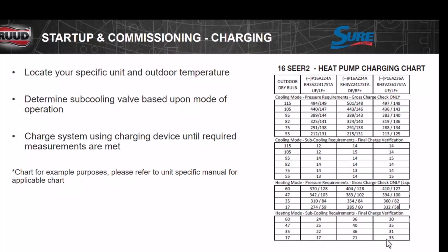While we're charging this in the cooling mode, we want to verify that we have a left-hand unit and we're running a 14 degree subcool. And then we come down or up to this chart and we look at our outdoor temperature at 82 degrees.